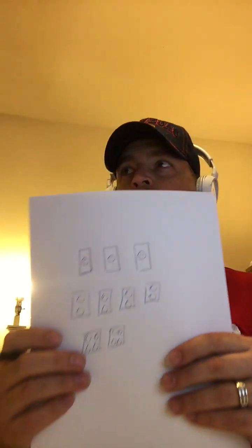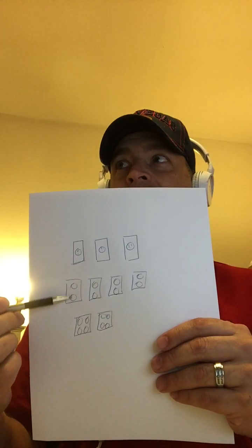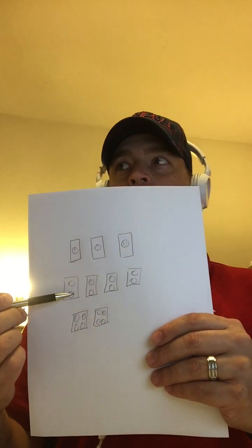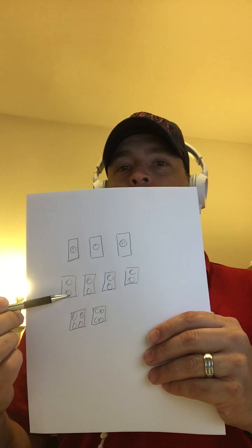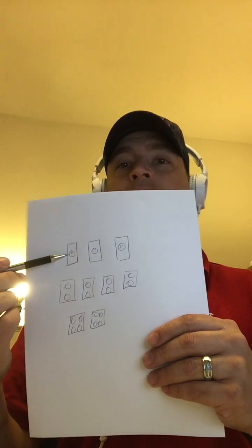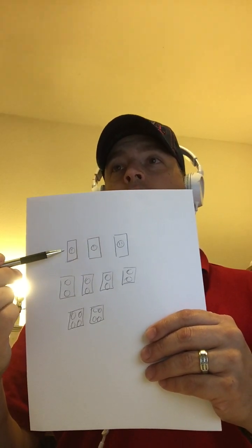Right after that, the second sentence in that section tells you that a single piece of equipment that has multiple receptacles, 4 or more, on the same piece of equipment changes from 180 VA per strap to 90 VA per actual receptacle opening individually. So these are still going to be the same, because 90 and 90 on a duplex are still going to be 180. Whether I'm doing that by the strap, the gang, or the receptacle, this is still 180 VA, but these up here would only be 90 VA per receptacle.